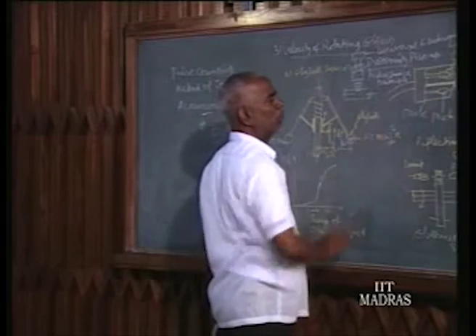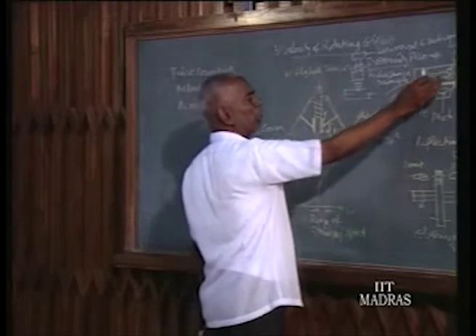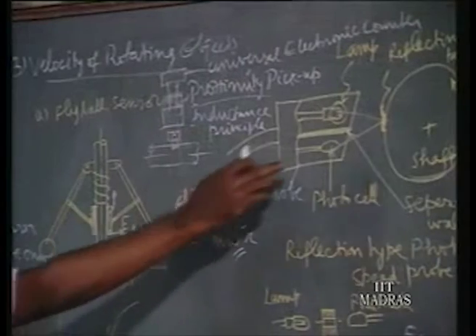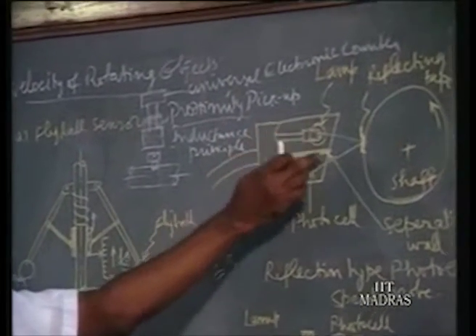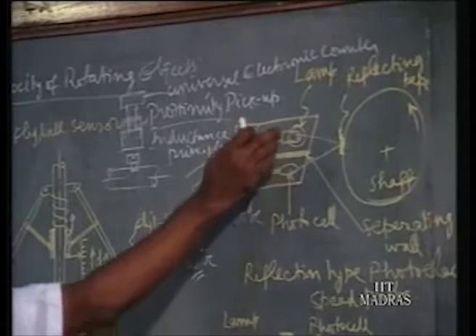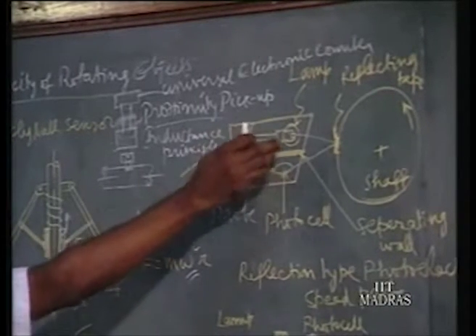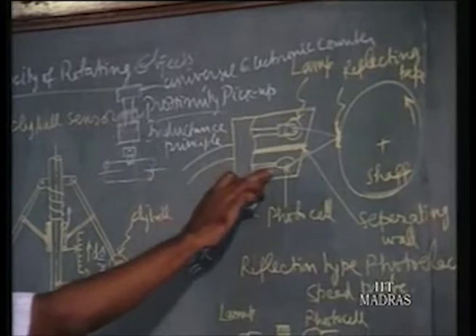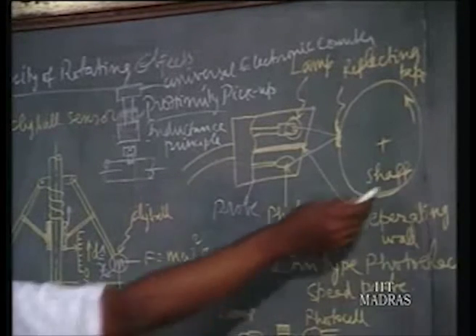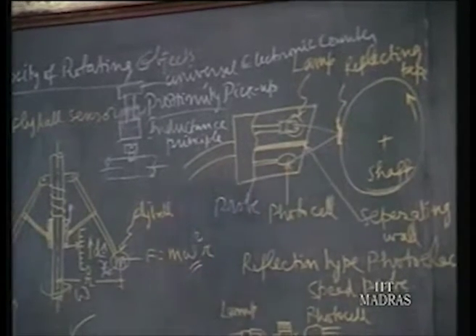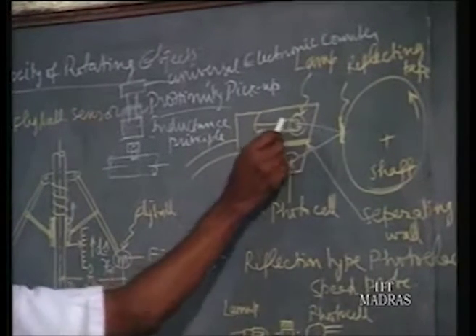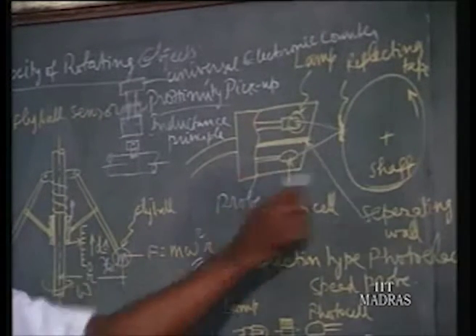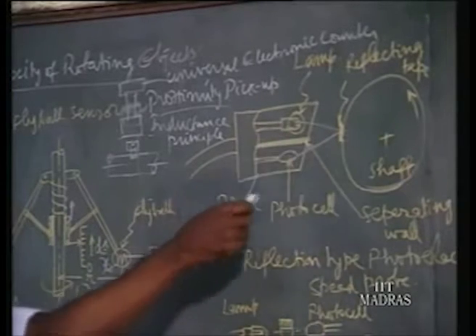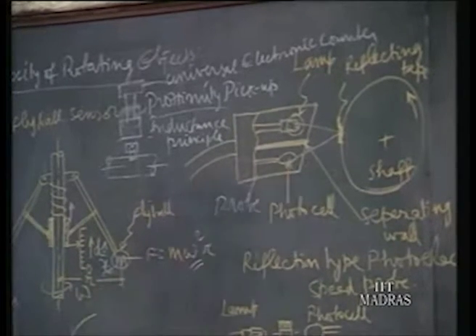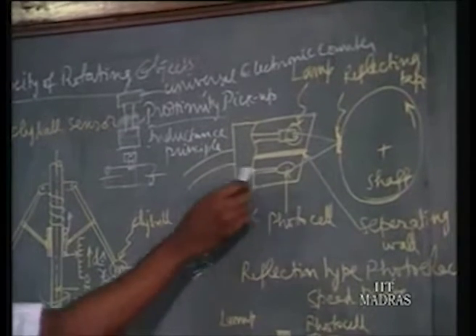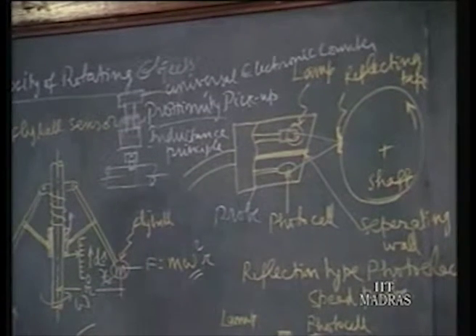In another method, instead of the inductance principle, we can have a light source. In this probe tip, we have a light source. It contains 2 chambers. In the top chamber we have the lamp, and in the bottom one we have the photocell. On the rotating shaft, we fix a reflecting tape, and the light falls on the tape and gets reflected. Whenever the tape comes in front of the probe tip, you get one pulse. The photocell forms part of an electronic circuit, so one electric voltage pulse will be produced.